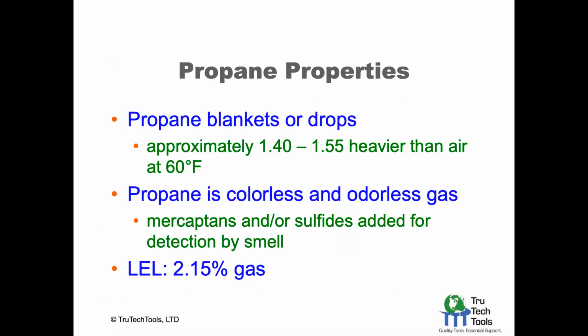Some other properties you need to be aware of between these two different gases. Propane is a heavier gas. It's got more carbon in it. It blankets or it drops. It's about 1.5 times heavier than air at 60 degrees Fahrenheit. Propane is actually odorless and colorless, but for commercial purposes, mercaptans or sulfides are added to detect it by smell. And again, that LEL is 2.15% gas.